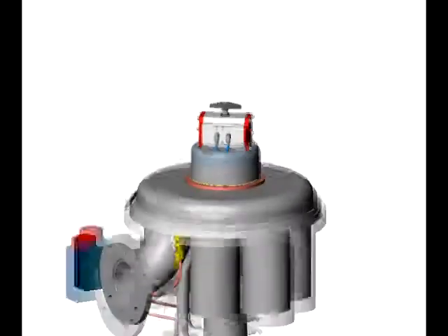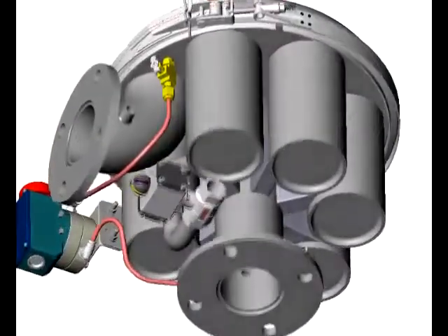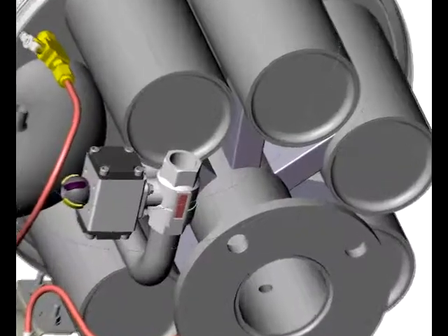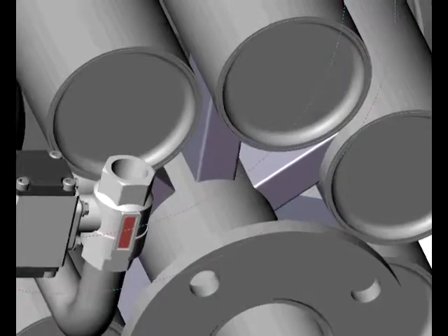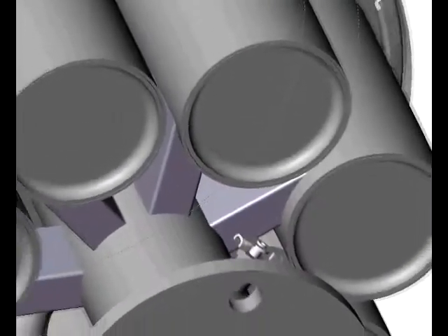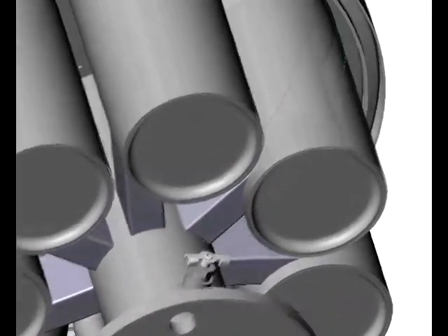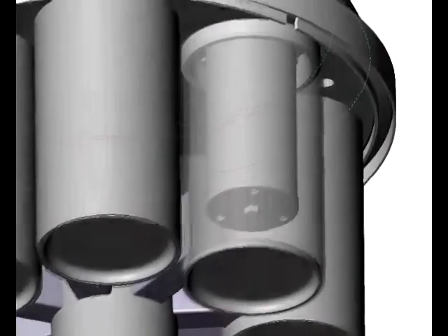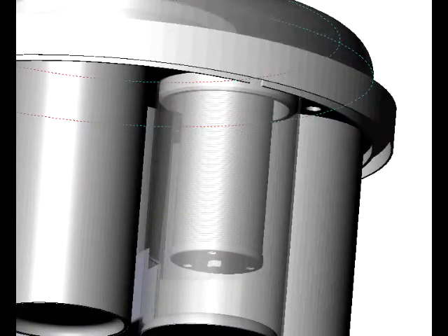Let's now look at the fluid flow paths in more detail. Dirty fluid enters the central column via the inlet flange. It then enters each of the six filter pods via the inlet galleries. The flow into each pod is tangential to impart a spin to the entering fluid. This turbo action serves to keep the debris away from the filter element, thus extending the time between backwashes.